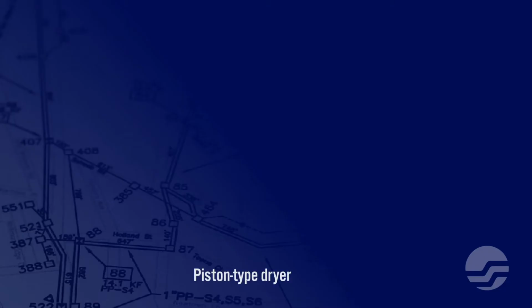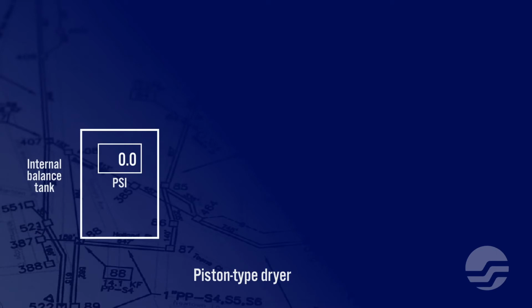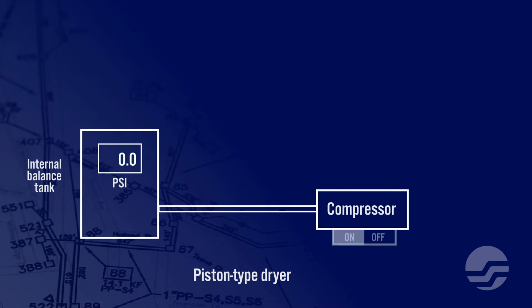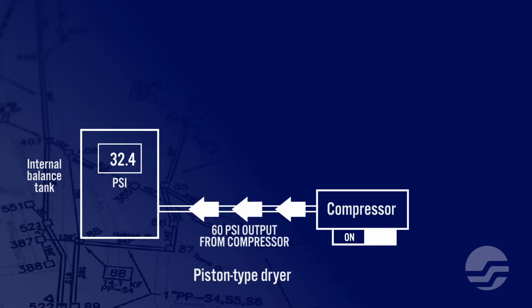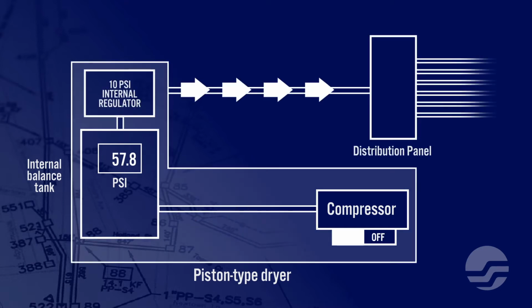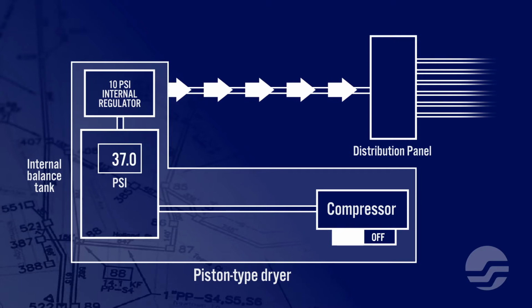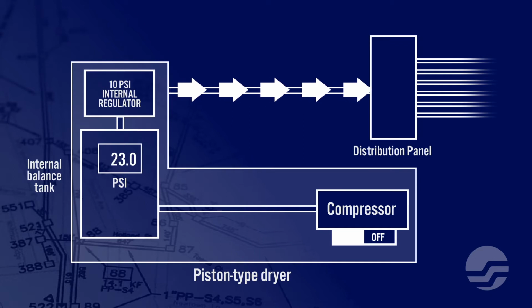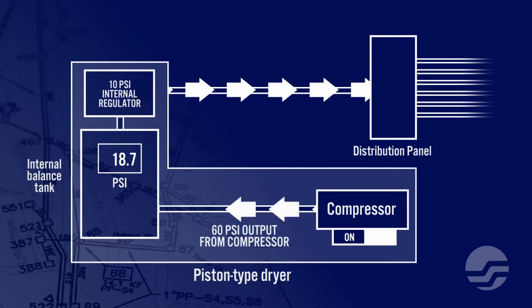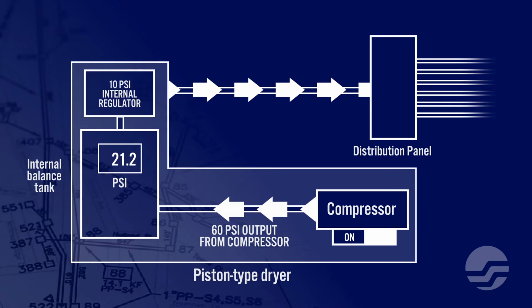Piston-type dryers have an internal balance tank that is filled on an as-needed basis by the compressor. The compressor operates at a constant 60 psi. Once the balance tank reaches 60 psi, the compressor stops running. The compressed air is slowly discharged from the balance tank into the distribution panel through an internal pressure regulator set to 10 psi. When the psi in the balance tank drops below about 20 psi, the mechanical compressor begins to fill the tank back up to 60 psi.